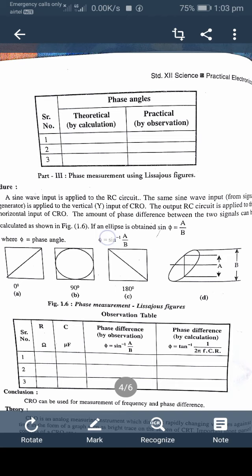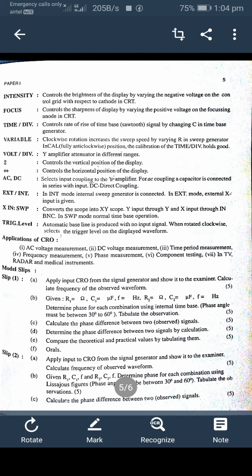The CRO is an analog measuring instrument which displays rapidly changing voltages against time in the form of a graph, seen as a bright trace on the screen of the CRT. Important front panel controls of the CRO include: intensity control — adjusts the brightness of the display by varying the negative voltage on the control grid with respect to the cathode in the CRT. Second is the focus control — adjusts the sharpness of the display by varying the positive voltage on the focusing anode in the CRT.